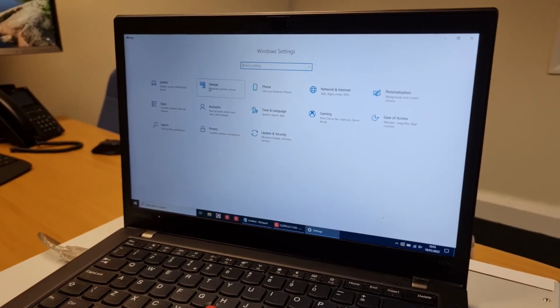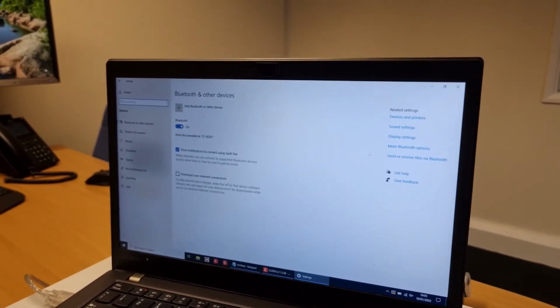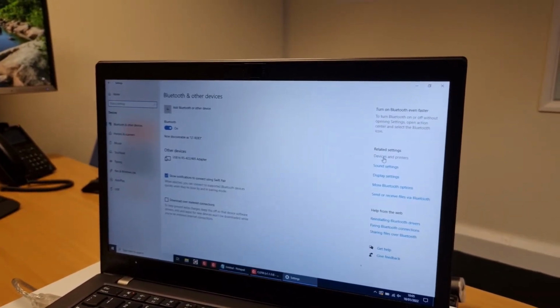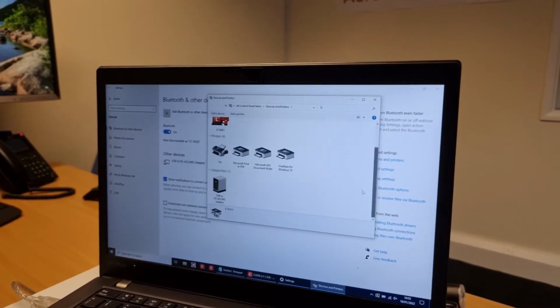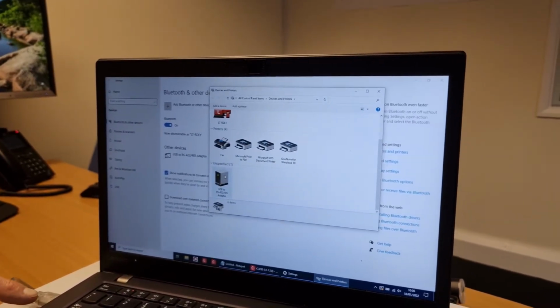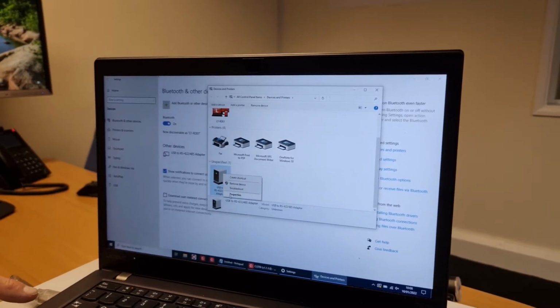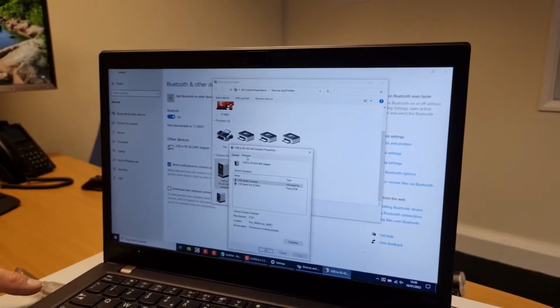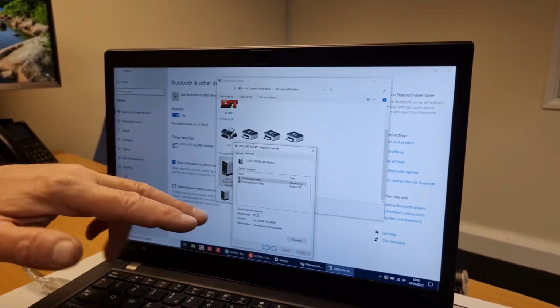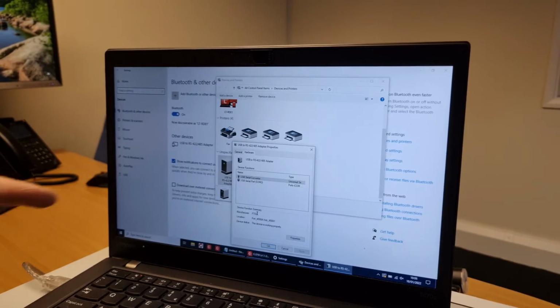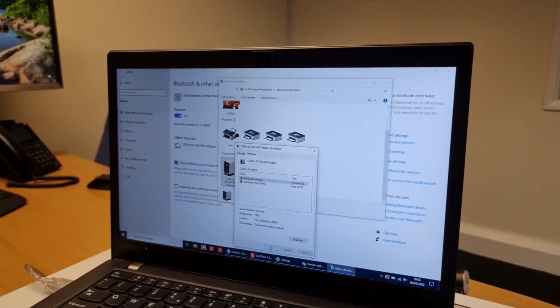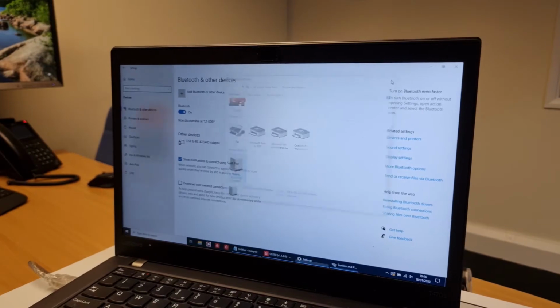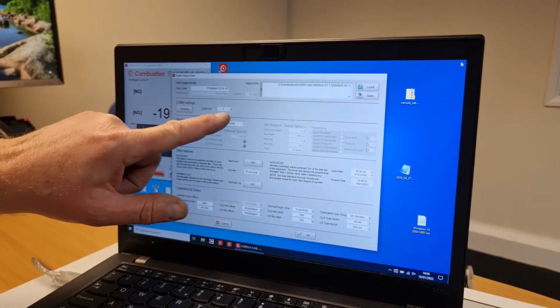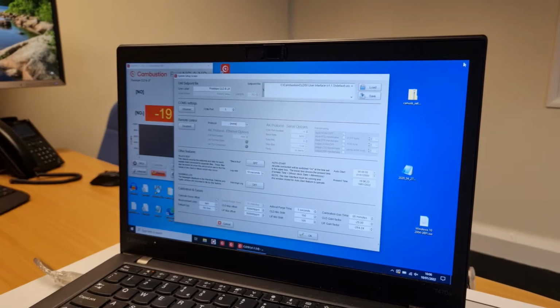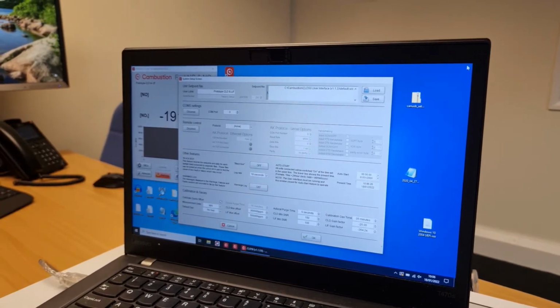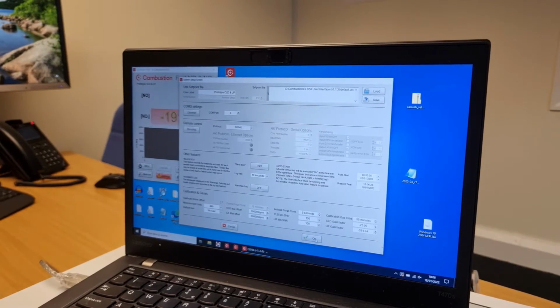If we look at our devices, we should be able to see our COM port for the RS232, which has been plugged in to one of our USB ports. If we look at the properties, that should match port 3, COM port 3. If you're providing your own laptop and it ascribes a different COM port number, you'll have to enter that into this box. And also you'll have to have installed the drivers for this USB to 485 converter, which will be sent along with the comms hardware.